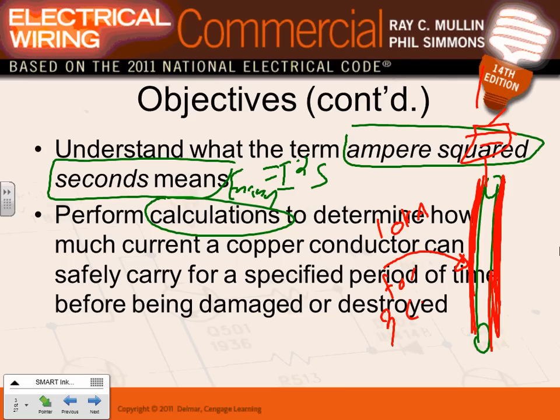We have to have a fuse here. Before that one ahead of it trips. That has to trip. What's going to protect your conductor? What protects the conductor is a fuse or a circuit breaker ahead of it. So if I set the circuit breaker at 10 kiloamps and interrupt at 3 cycles or less, I am guaranteed that this fuse, set at 10 kiloamps, 3 cycles, and the conductor can withstand 10 kiloamps, 3 cycles, right? So the fuse will trip at the right value and at the right speed before the conductor turns into a big ball of fire. Typically, you don't want to sit it like this. It will probably be set to trip at one cycle or faster than that.